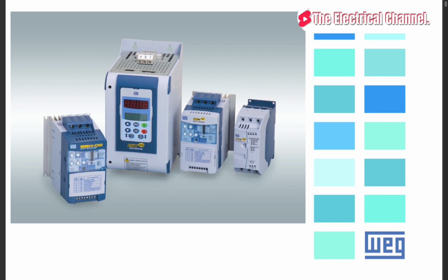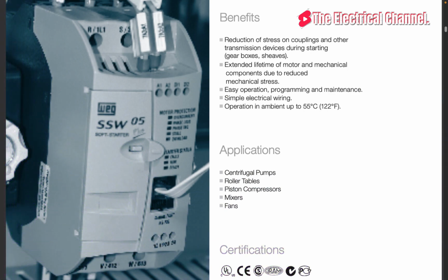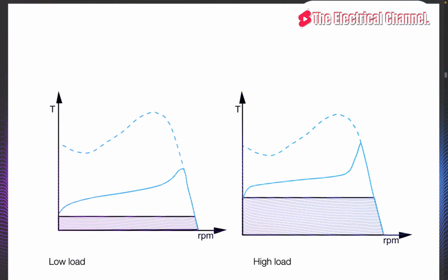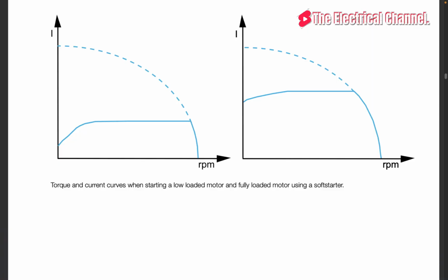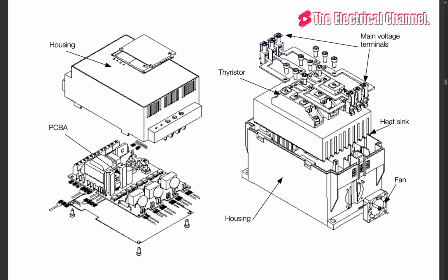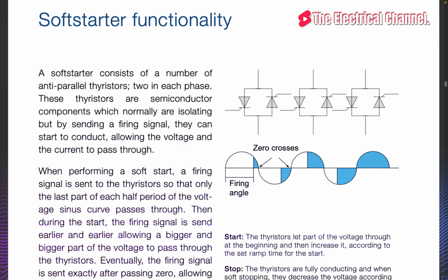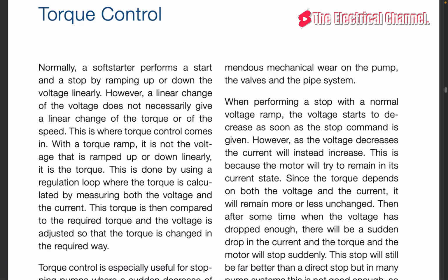Since the voltage to the motor is reduced during start, both the current and the torque will also be decreased. In fact, if the voltage is decreased to 50% of the full voltage, the current will be decreased to about 50% of maximum current, and the torque would be decreased to about 25% of maximum torque.